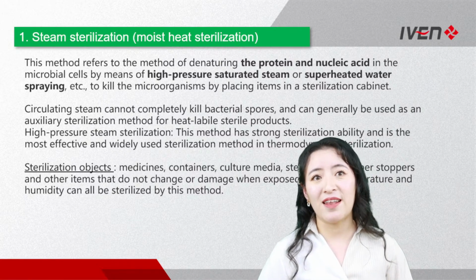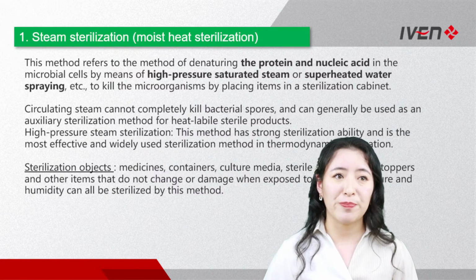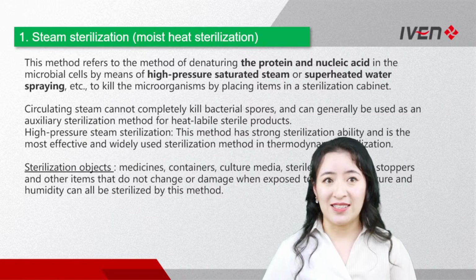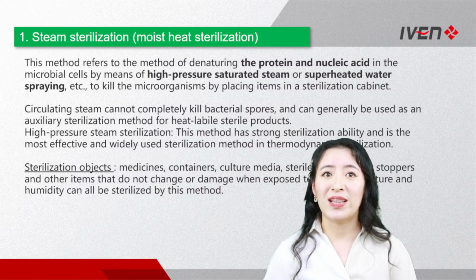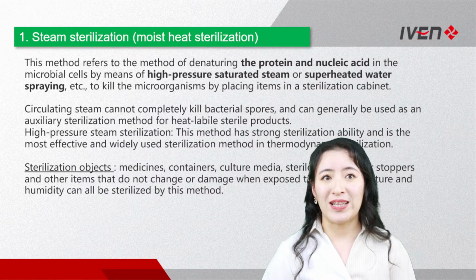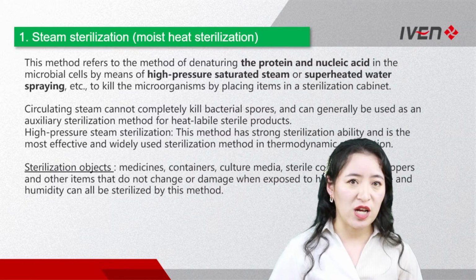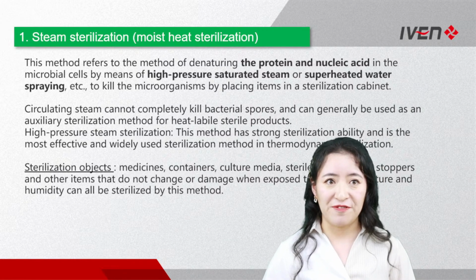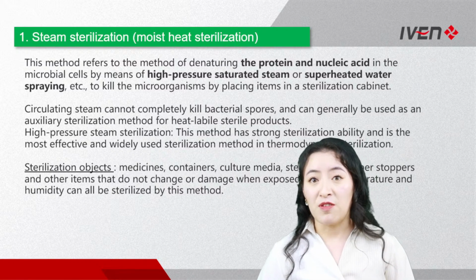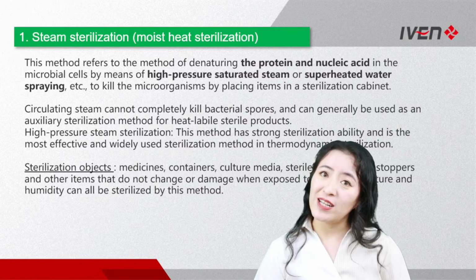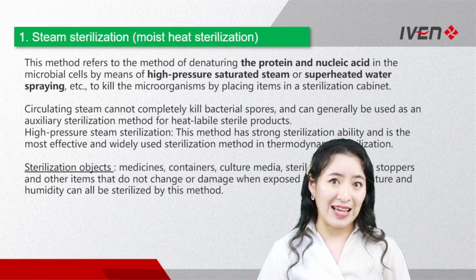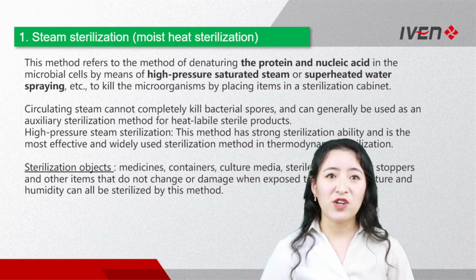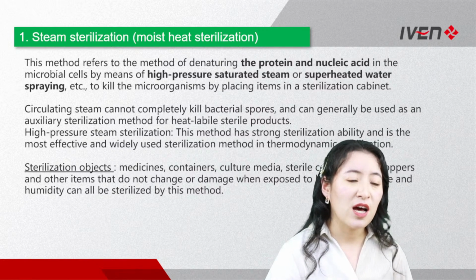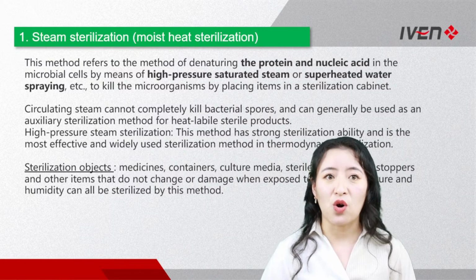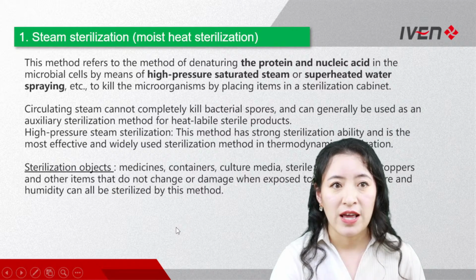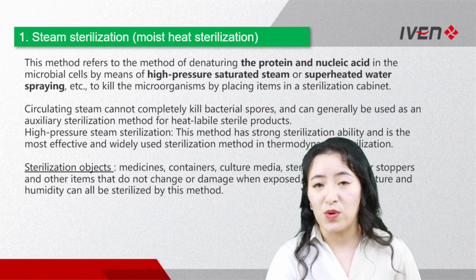Circulating steam cannot completely kill bacterial spores and can generally be used as an auxiliary sterilization method for heat-labile sterile products. High pressure steam sterilization has strong sterilization ability. So this one is more useful, more effective and widely used in our pharmaceutical industry. Which kind of products will we use this method to sterilize? For example, medicines, containers, culture media, sterile clothes, rubbers, and other items that will not change or be damaged when exposed to high temperature. These kinds of things can be sterilized by this method.